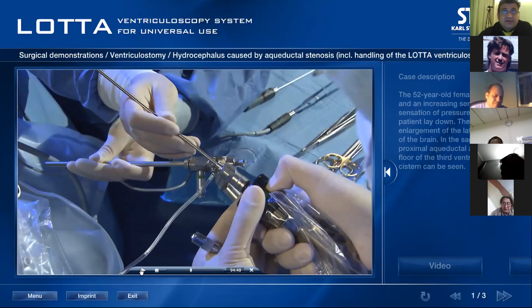Now, when you change, make sure that somebody is standing at the video monitor trolley and reduces the light source. There is a button which you can put on the standby mode, because if this light source is not reduced, it's a xenon high intensity light source. It can come on the surgeon's eyes and make him uncomfortable, or even if it is kept on the sterile drape, it can burn it off. So now we are connecting the 30-degree to have a complete diagnostic ventriculoscopy.